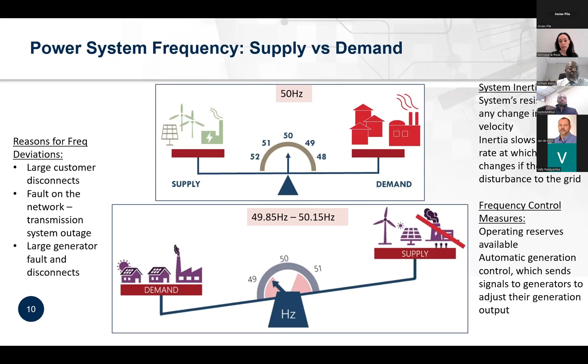So inertial energy, as I said, is defined as a body's resistance to change of motion. The generators are spinning, and they've got massive energy stored in them. So if there's a small change on the system, it's not going to impact the system frequency. These synchronous machines, the baseload power, coal, hydro, assist in keeping the electric power system's frequency stable. And as these are displaced by renewable energy generators, there will be a higher erosion of system inertial energy. And Jan also touched on this: the rate of change of frequency will increase. So if you see a disturbance on the network, your frequency will deviate quickly, either going down or going up, and that does put the system at risk. But the work that we do looks at this and at the impact of this going forward, so that if there are changes that need to be made, these can be done and mitigated for properly.